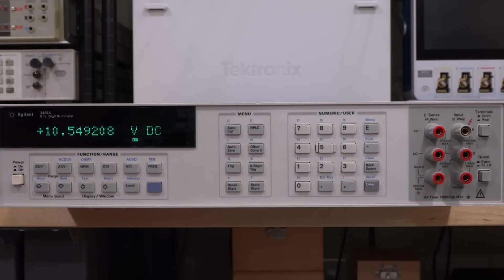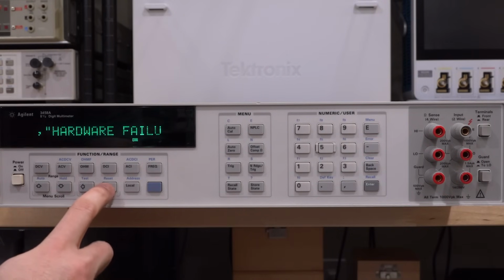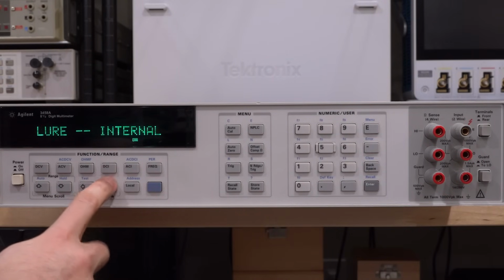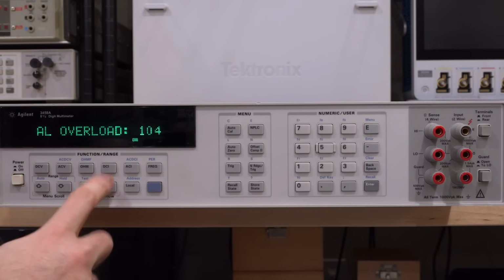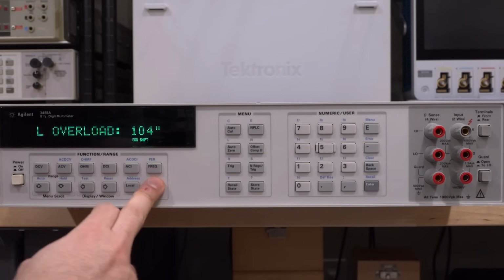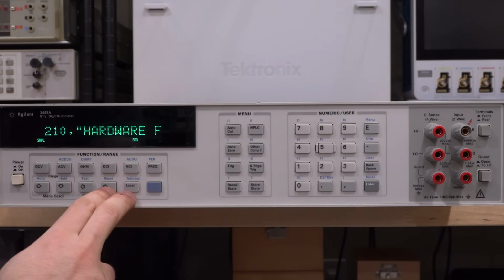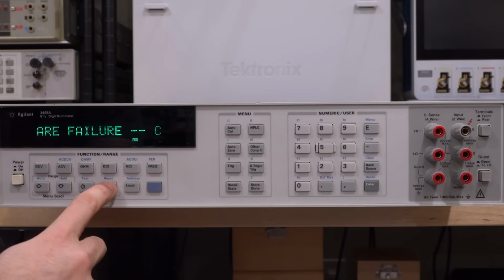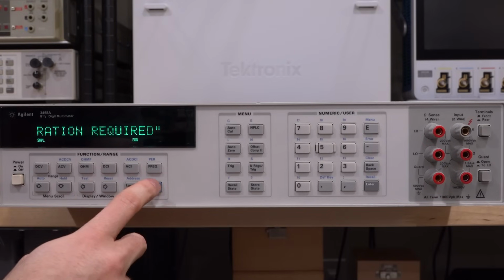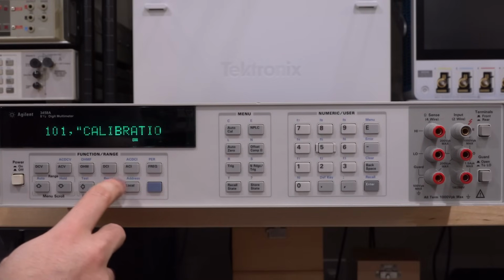So we went through the voltage calibration, but then as soon as it hit the resistance calibration, it immediately generated an error. So if I go and look at the error in this case, it says error 209, hardware failure. That's not good. And then internal overload 104. Okay, is that the only one? And then there is error 210, internal hardware failure again. Yes, there we go. Yes, calibration required. We know that one. Any more?